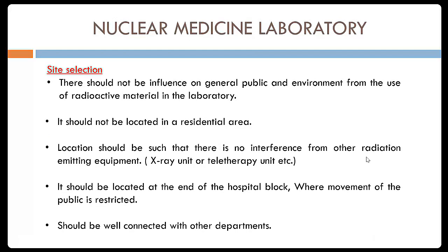So before going to that, we should know about the nuclear medicine lab, where we do this process. The first thing we have to take care of is the site selection. There should not be any general public in the area, and it should not be in a residential area. And there should not be other X-ray radiation emitting equipment nearby, like the X-ray unit, CT, fluoroscopy, and all. So those departments should not be near this unit.